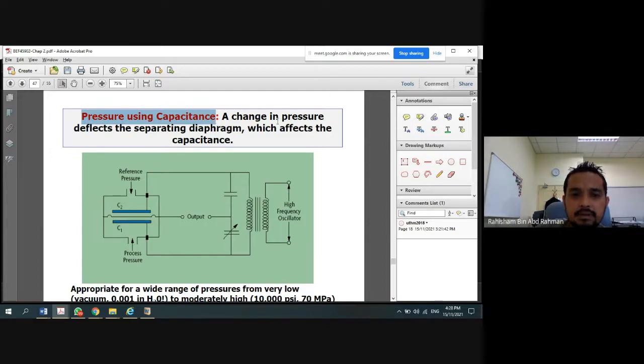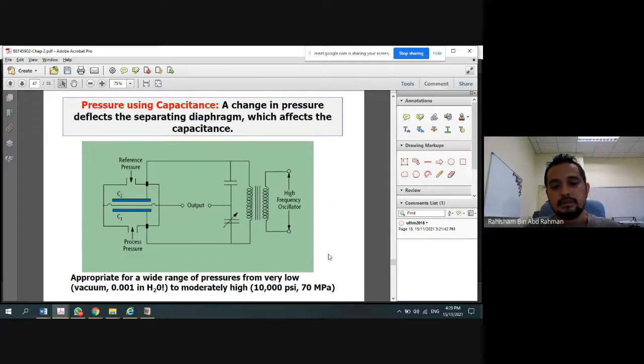A change in the pressure deflects the separating diaphragm, which affects the capacitance. We have pressure 1 and pressure 2. Of course, one will be a reference pressure and the other is the measured pressure. Once we have the pressure, it will change the capacitance value, and this capacitance value will be converted by the electronic circuit here so that we can see the output. To a certain level, we may need to amplify the signal so that it is readable.